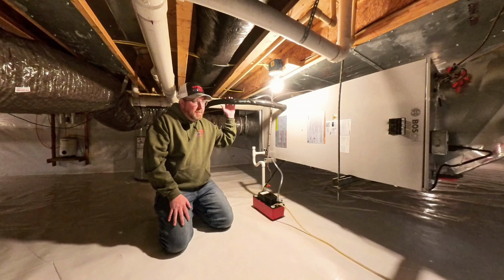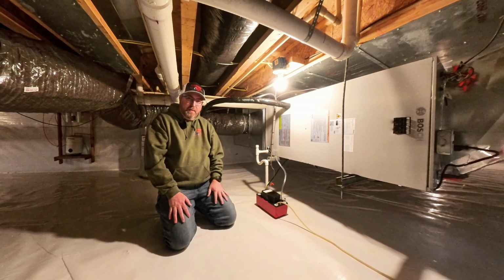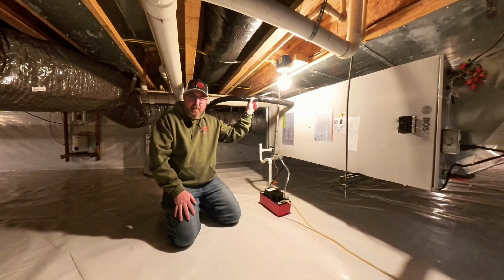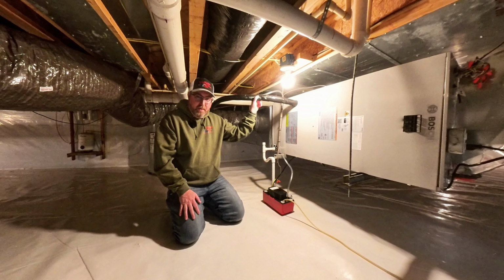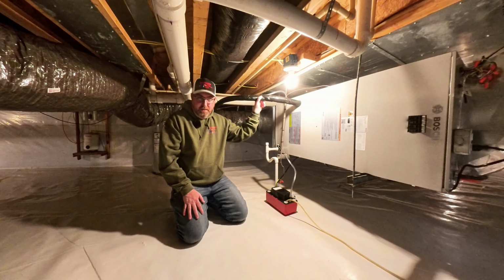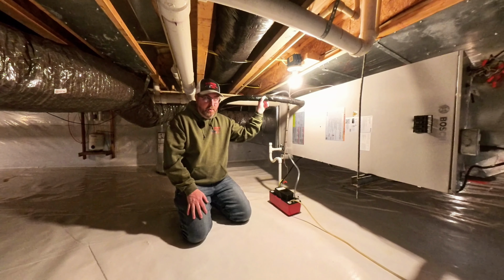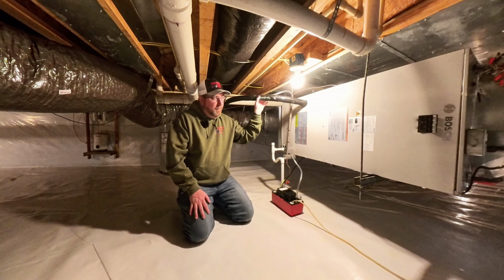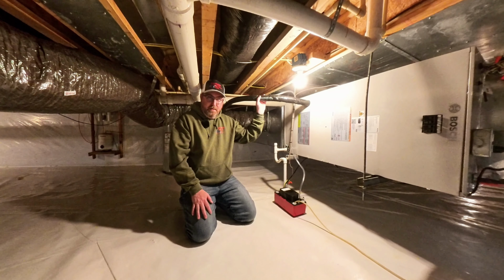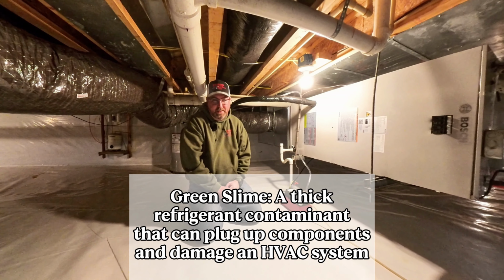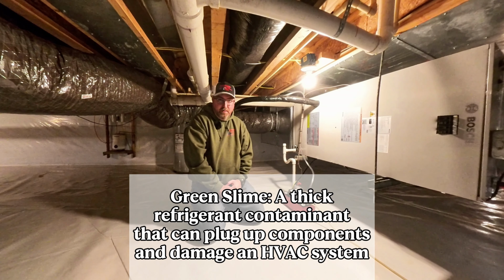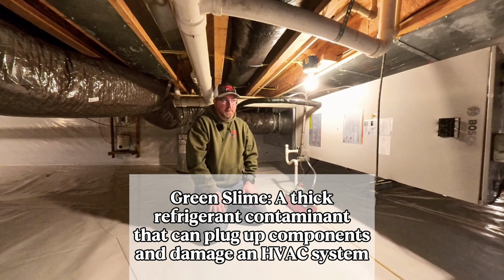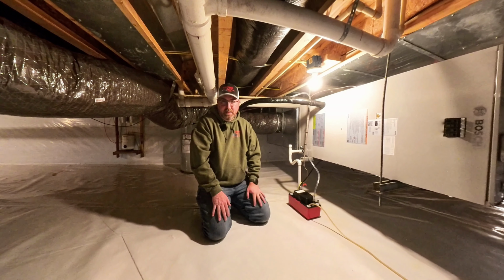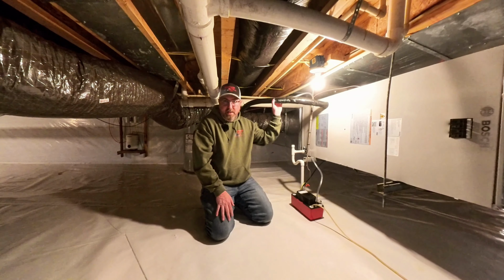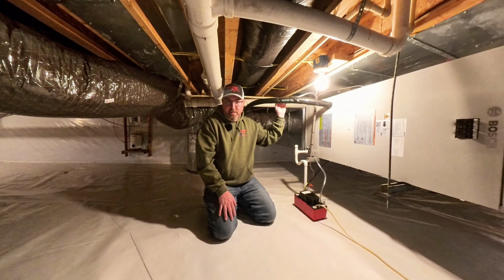supply those. Originally, we had planned on and quoted the customer to reuse their refrigerant line set. The customer had an original complaint of a compressor tripping the breaker continuously. We did not re-diagnose the system. The customer just wanted a quote, but once we recovered the refrigerant and opened the line set, we saw evidence of green slime or something inside the system being green, whether that be dye or green slime. Neither one of those we want to put through a new system, so at that point we decided to talk with the homeowner about replacing the line set so that we would have a nice clean, fresh line set, so we would not contaminate the new system at all.